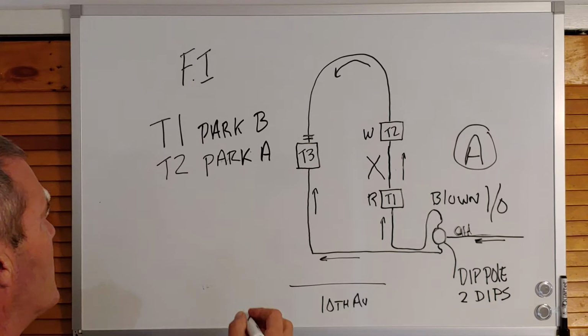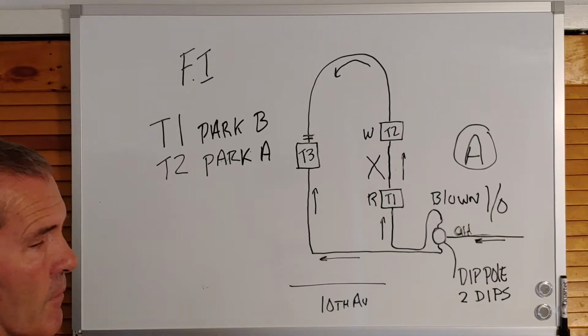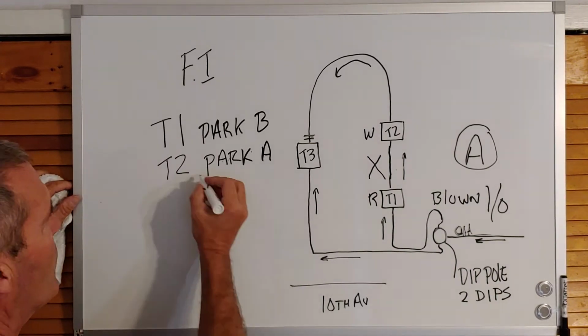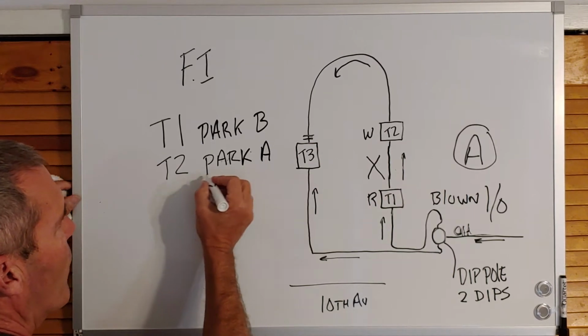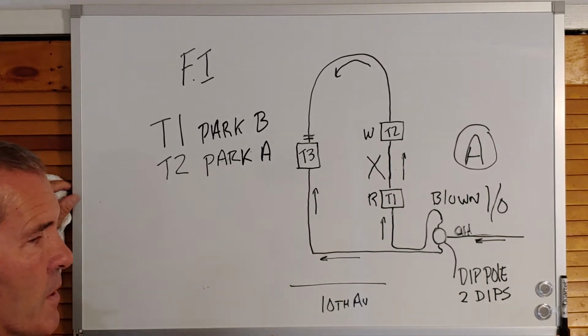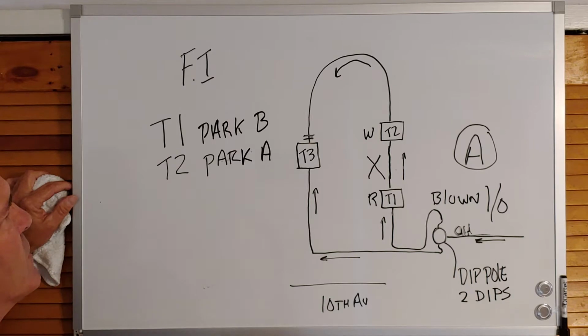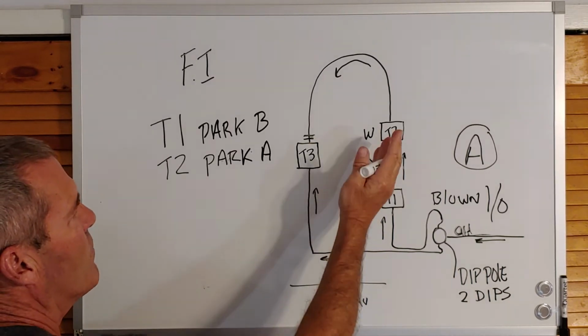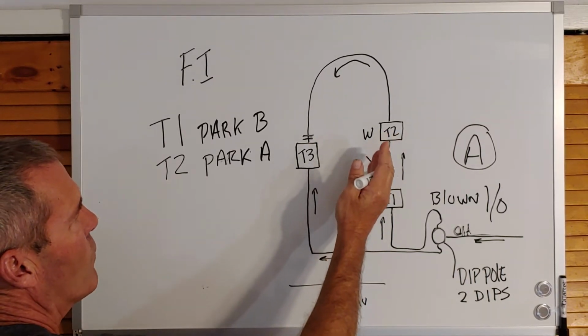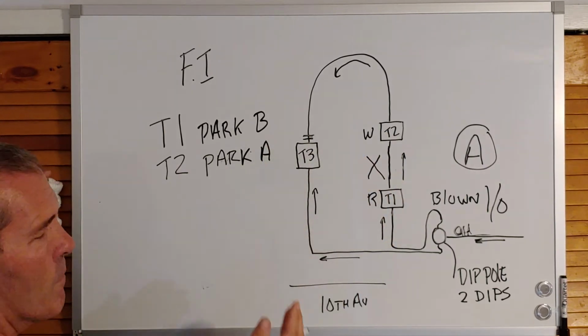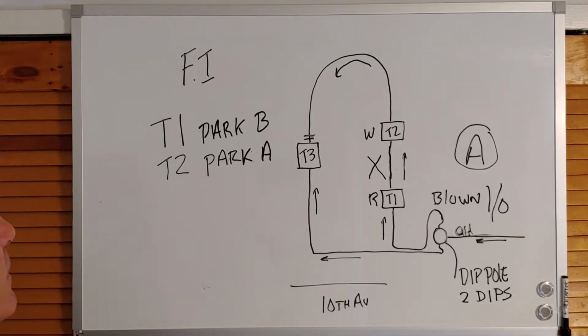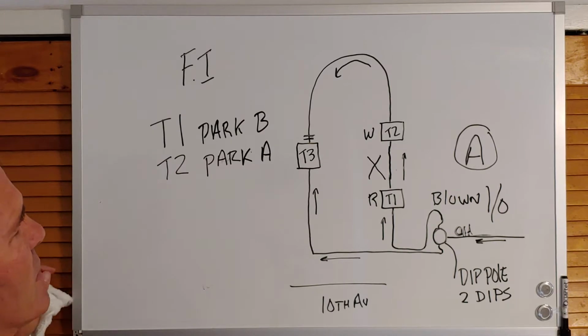Just a short explanation here. If you've kept up with the videos and the quizzes, you know what parking is. Parking is using that one bushing parking stand, mounting it in the transformer, and moving that inbound cable elbow that went in on A and parking it. Parking it is dead ending the conductor and isolating it.